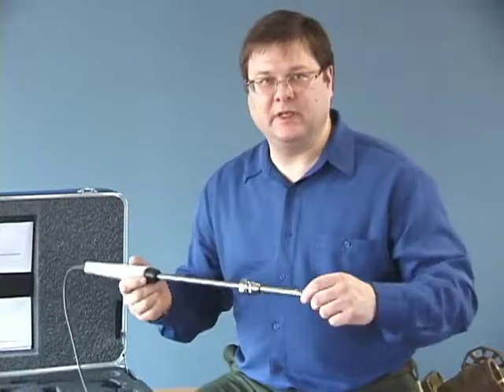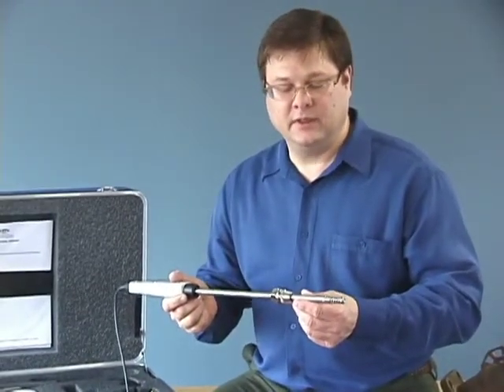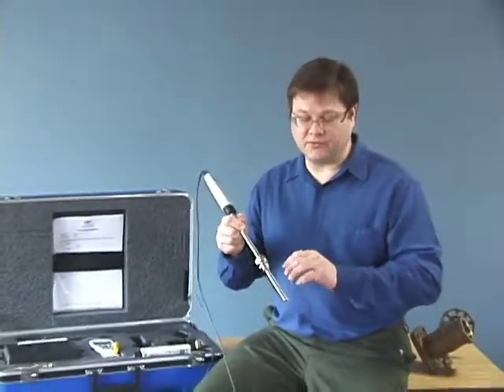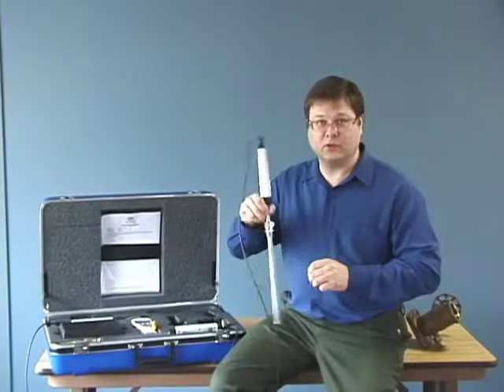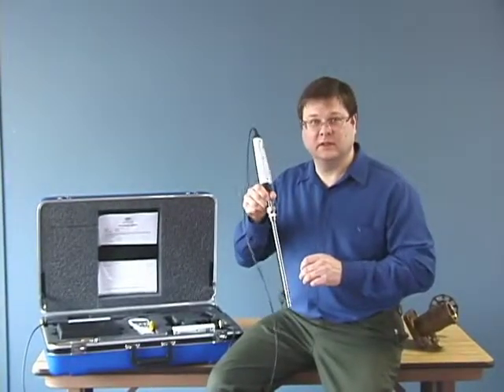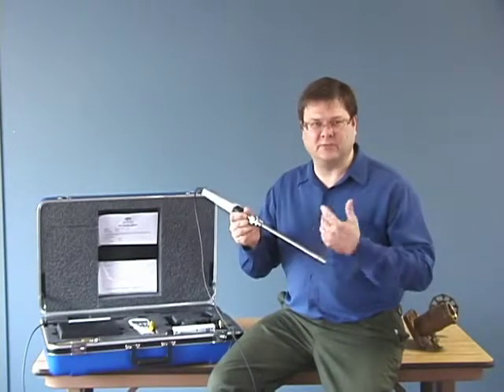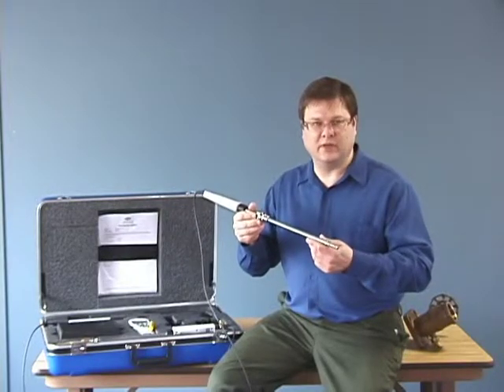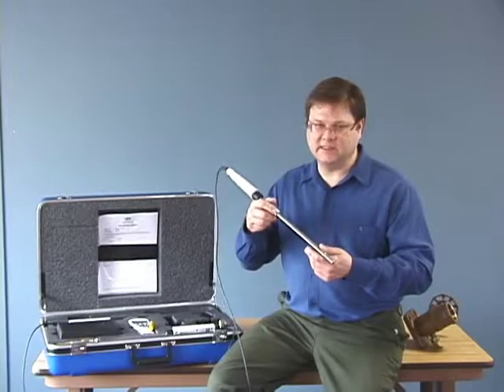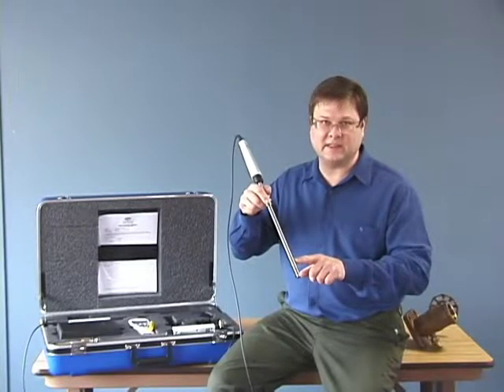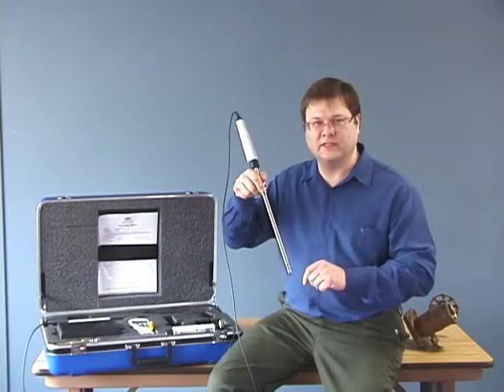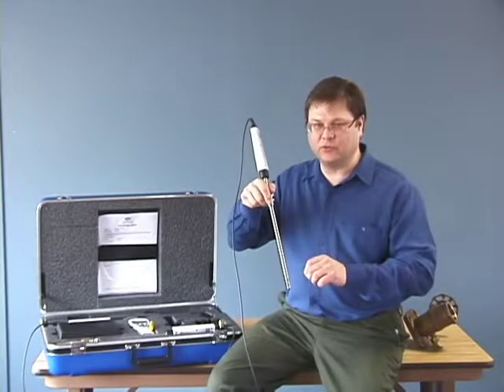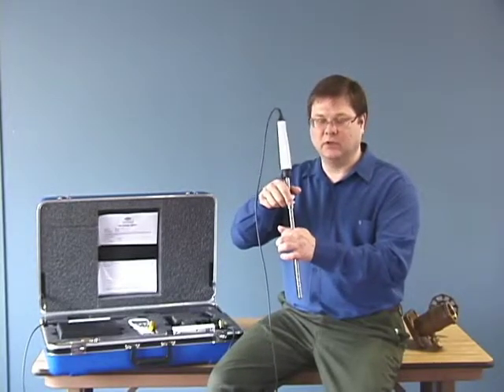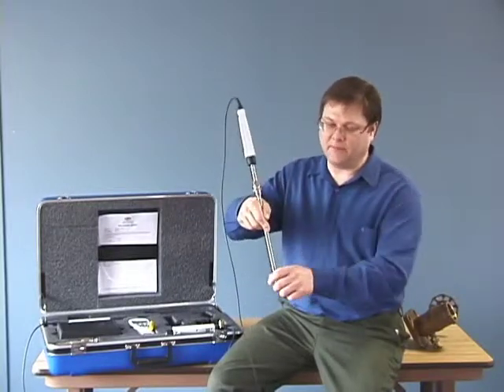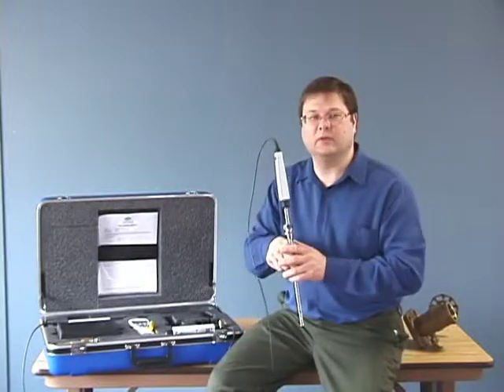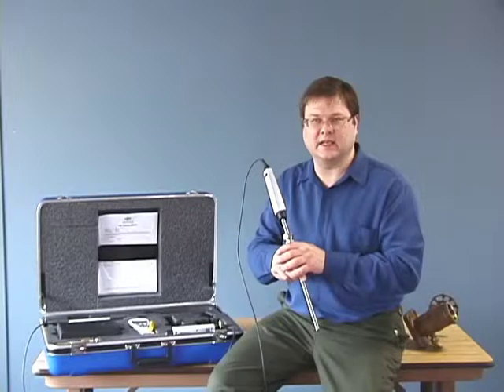Okay? Some people ask me if we can do oil samples in a jar. And yes, we can. The easiest way to do that is to put the oil sample in the jar and just put the probe in and swirl it at about this rate for about 60 seconds. If it's a plastic jar, I wouldn't really recommend it because plastic tends to absorb moisture and the reading will be constantly changing. However, if it's a glass jar, it's easily done. Just make sure that the oil level is at least past the sensor head, and that when you're swirling it, you don't pull the sensor out of the oil. In addition, if the sample jar has just a small hole at the top, what you can do is take the whole thing by the top and just swirl it like this in order to get a reading. And like I said, it takes anywhere from about 30 to 60 seconds.